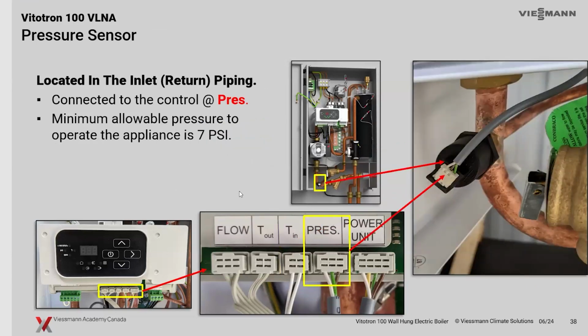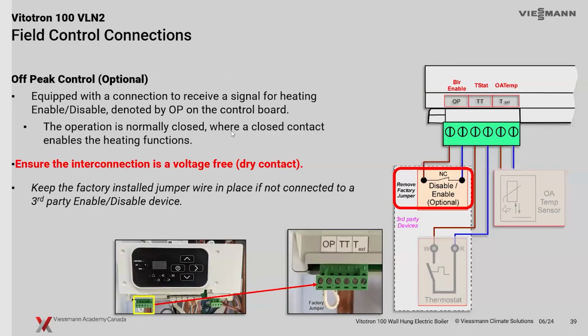All right, a little pressure sensor, as I mentioned. You can turn this off if you want. It's in the advanced programming of the interface, but it is set for 7 psi, and you'll get a fault if we're down below that 7 pounds of pressure. So the pressure sensor is connected directly to the system at the bottom there. And some of the things you might want to use an electric boiler for, obviously it's connected to your utility, so directly your power contact here.